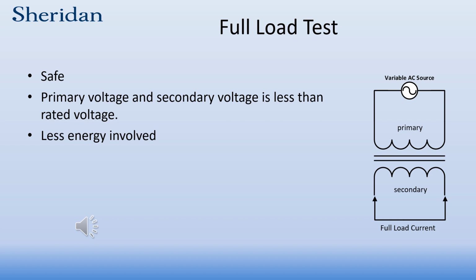The advantage of doing this is that the amount of energy we're using is much less than would normally be involved if we put a standard load across the secondary of the transformer and used rated voltage on the primary. This makes this type of test actually safer.